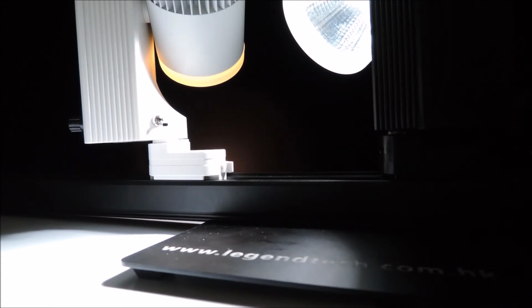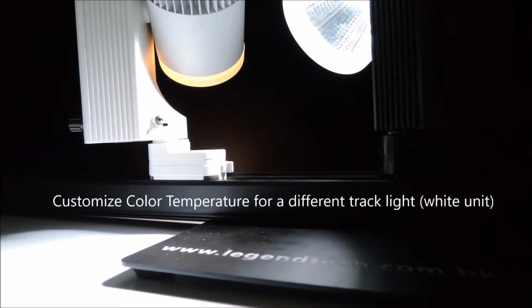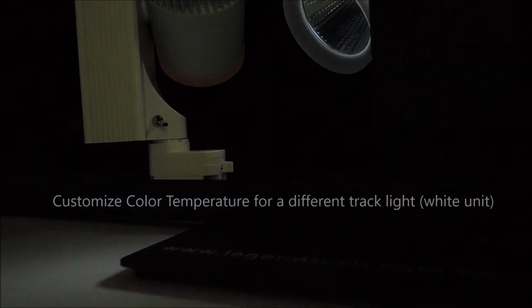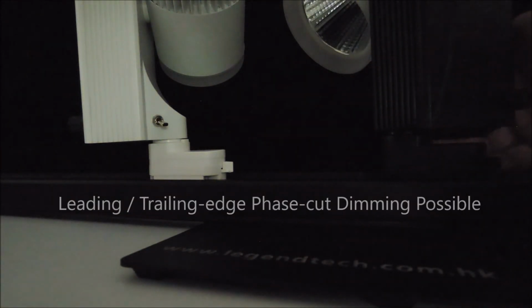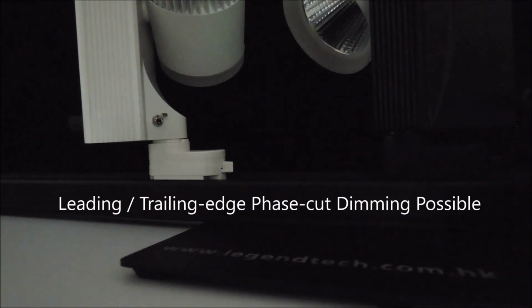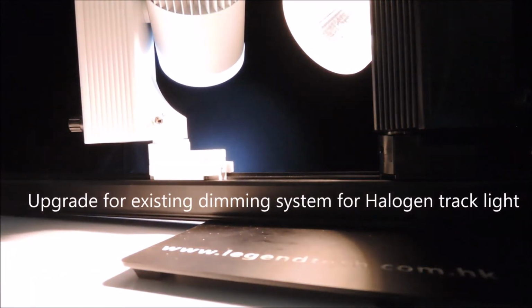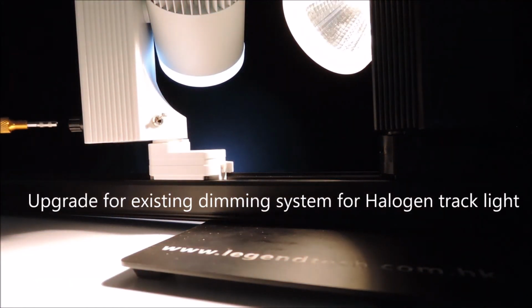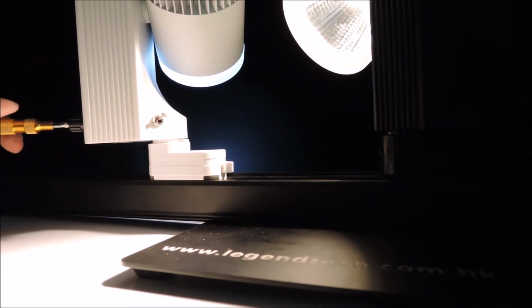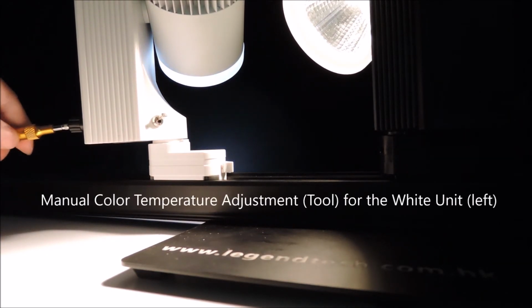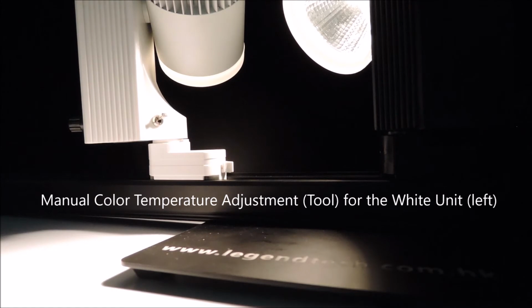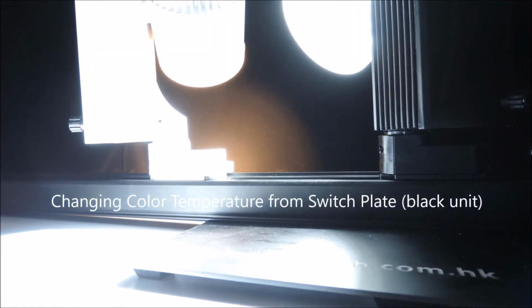And let's do it with the white unit on the left. Last but not least, our 20 watt track lights can be controlled by either a leading or trailing edge phase cut dimming signal. So our tunable track lights can be considered as an upgrade to an existing dimming system that already has leading edge dimming control in place, or that was originally designed for halogen track light sources.